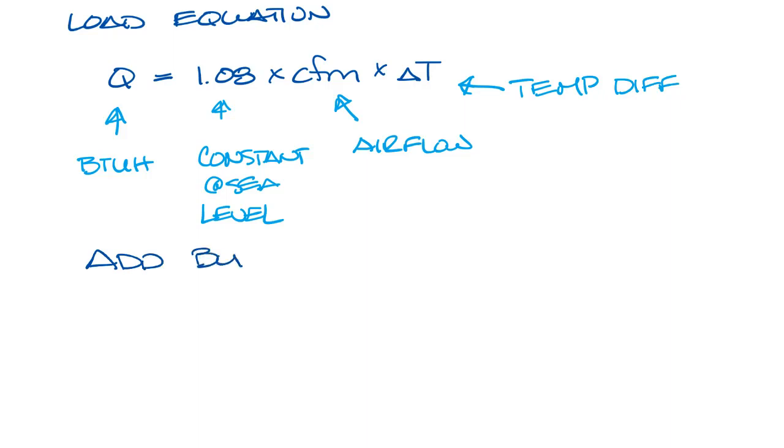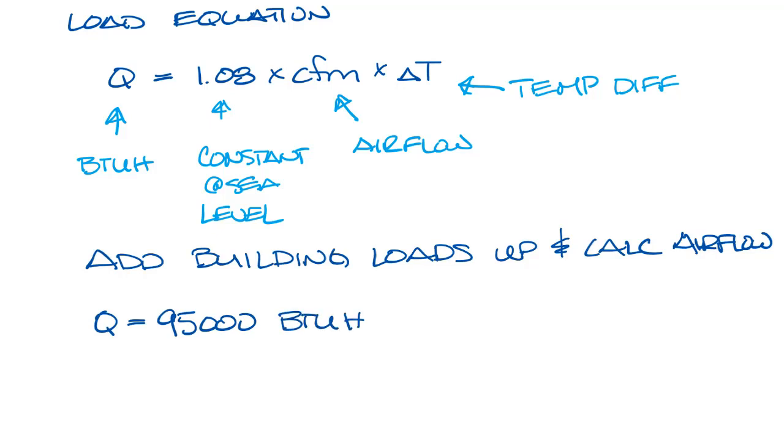So if you add all your building loads up, you can calculate the air flow. So let's say that we have a building, and we've already added the loads up, and they come up to 95,000 BTU. And we know we want to supply 55 degree air, and we want to keep the space at 75 degrees.